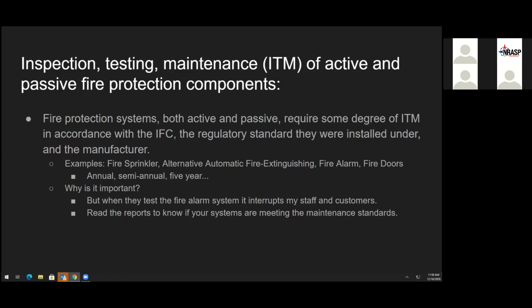Sometimes I see on a report that the fire alarm was tested, but they chose not to test the notification because it was going to disrupt the staff and the work day. My message to you is when they test your fire alarm system, make sure they are completely testing it, because I would hate to hear that your fire alarm system activated, but the notification devices didn't go off, and we didn't know because we've told them not to test and make noise for the last 5 years. You need to make sure that all of your systems are being tested appropriately.